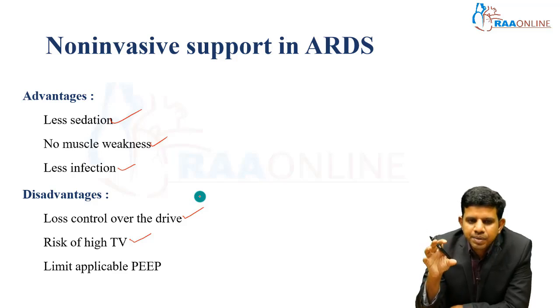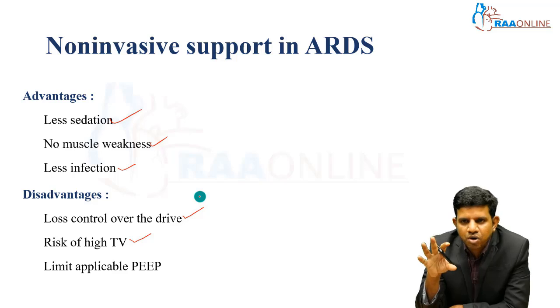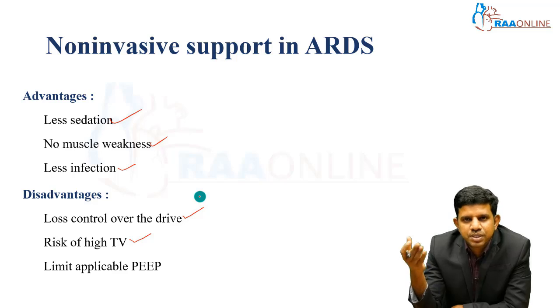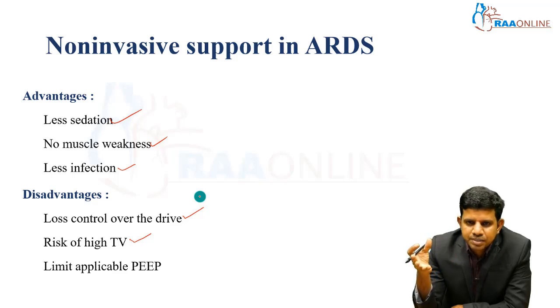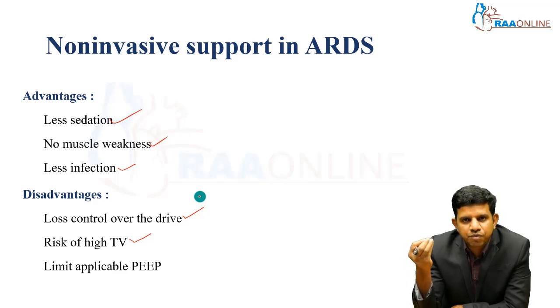The second thing is the limit on applicable PEEP. For example, with non-invasive mechanical ventilation, especially when delivering non-invasive support through the NIV mask, you can deliver a PEEP of 10. If you increase the PEEP to more than 10, the leak will increase. It cannot be delivered to the patient. The leak will increase, the positive pressure won't reach the lung, and the patient won't tolerate that. For example, in a patient with severe ARDS with a PF ratio of 60, you cannot deliver the required PEEP through non-invasive mechanical ventilation. These are the disadvantages of non-invasive support in ARDS.